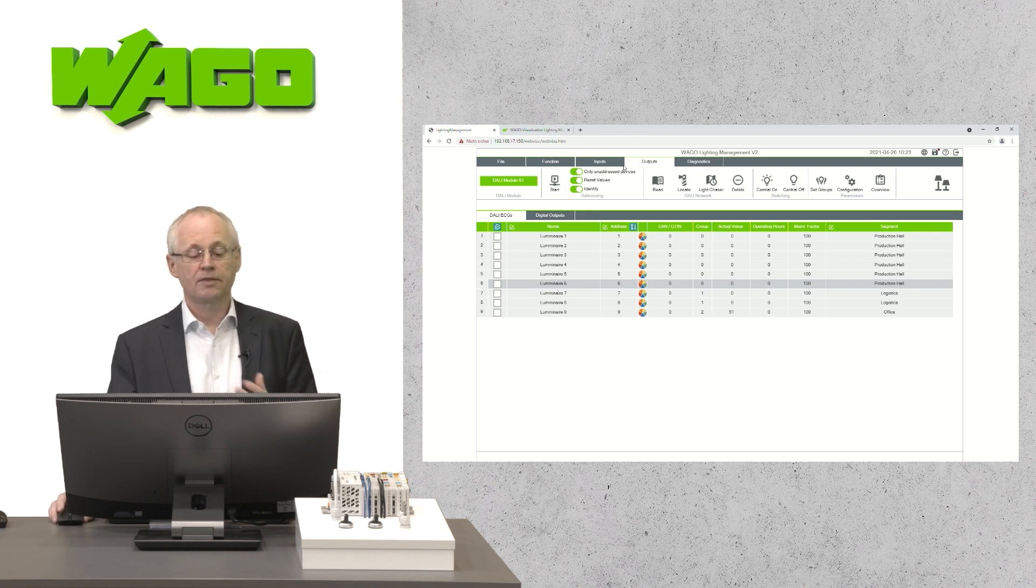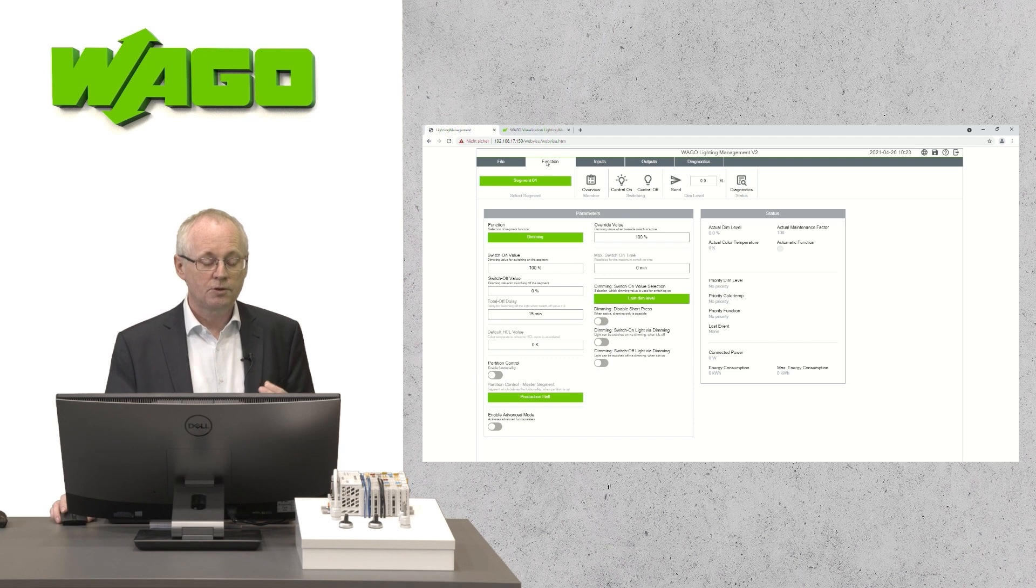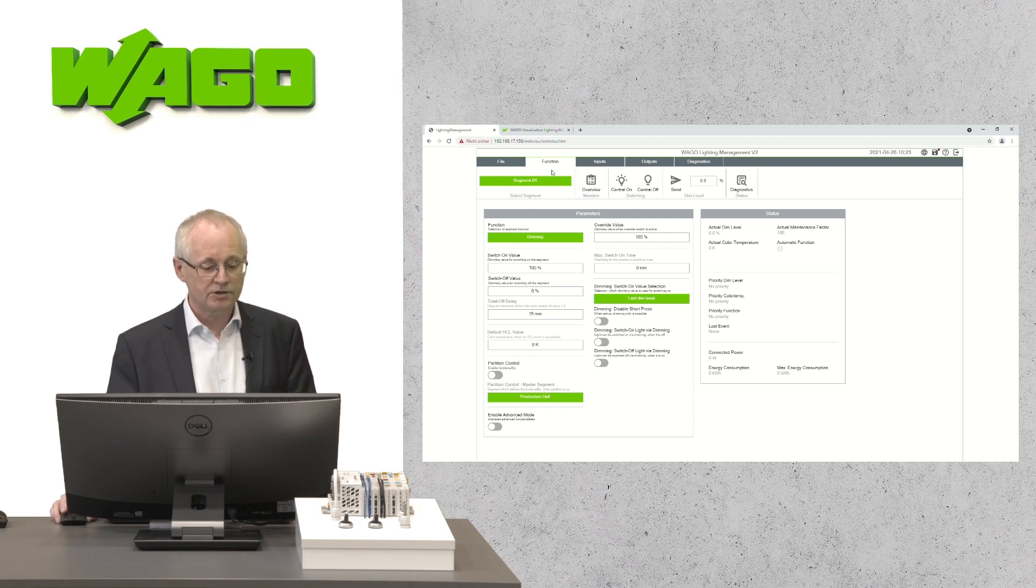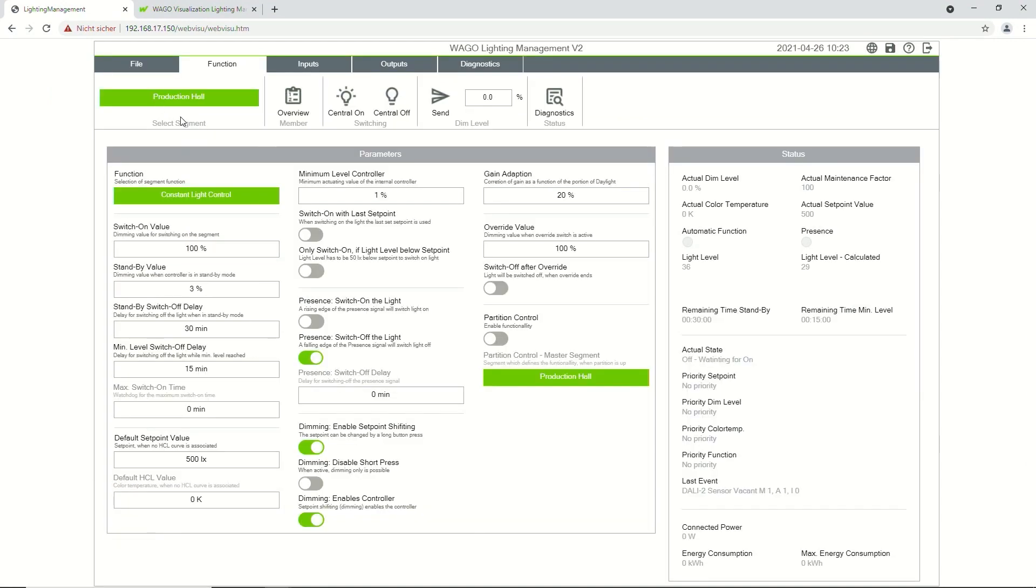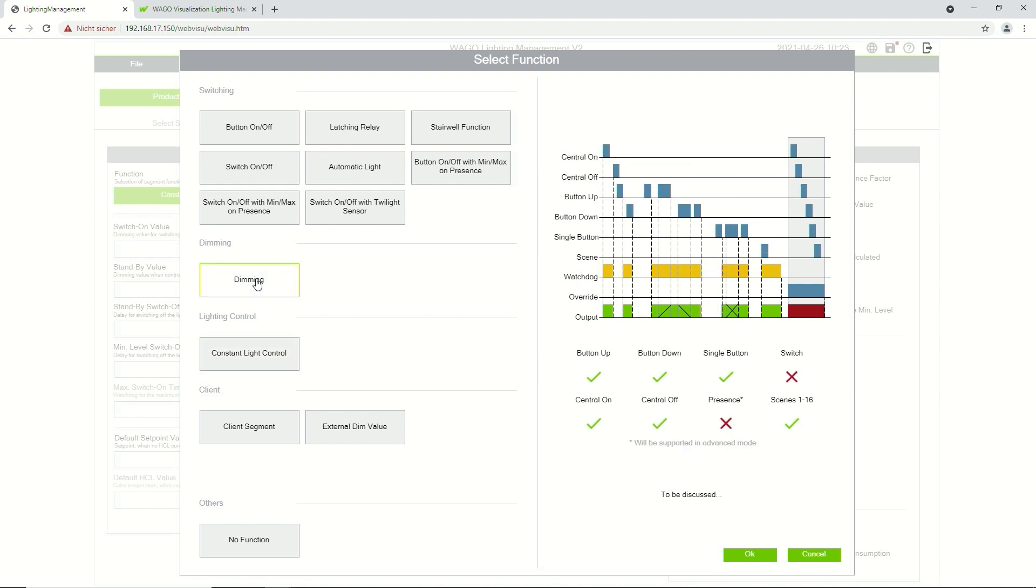After the configuration of the inputs and the outputs, you will be able to define the functionality. Therefore, we switch to the tab functionality. You can select a segment and a functionality for this segment. Different types of switching, dimming and also constant light control, for example. Depending on which function you select, a graphic here on the right side of the screen will illuminate the functionality in detail.